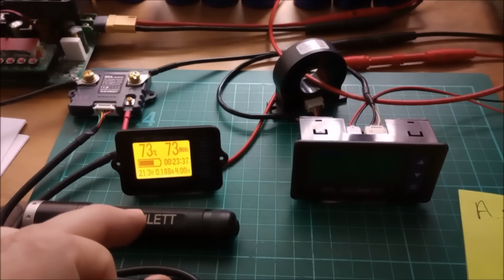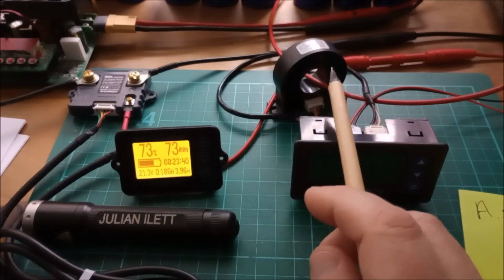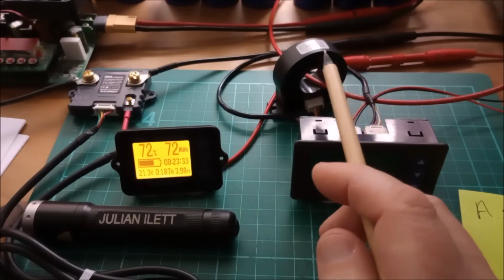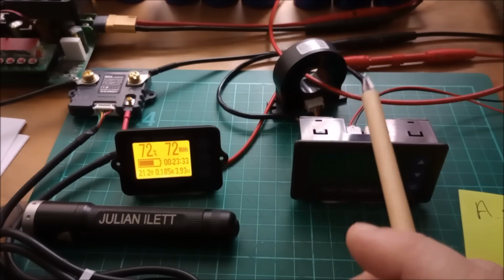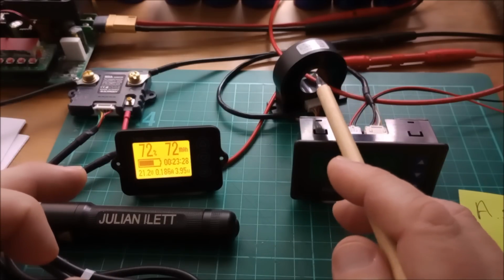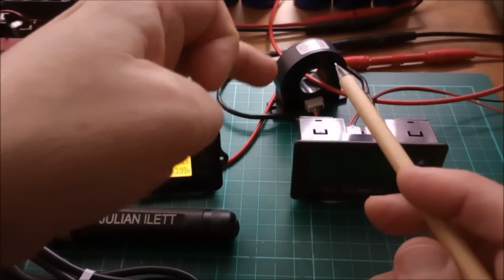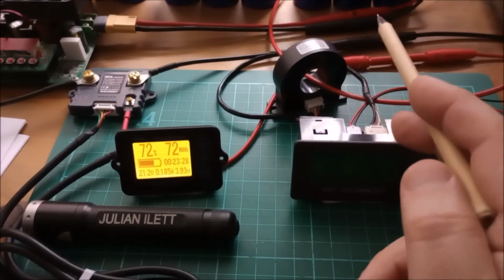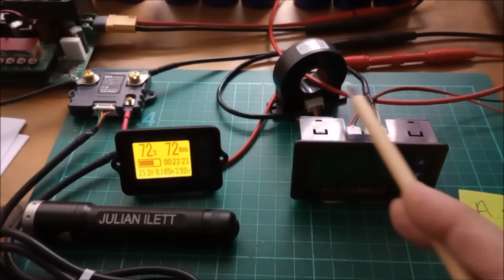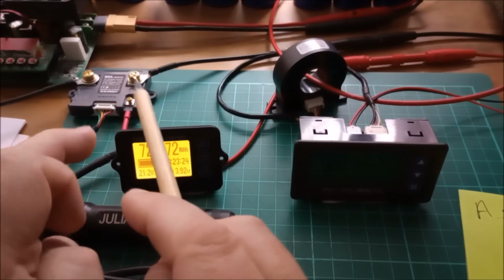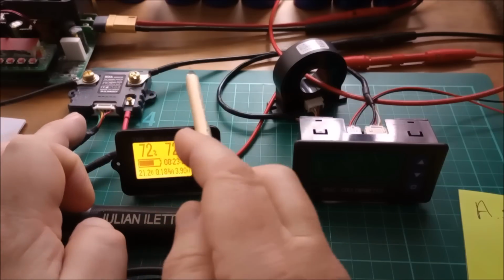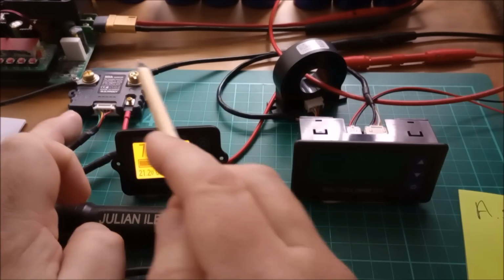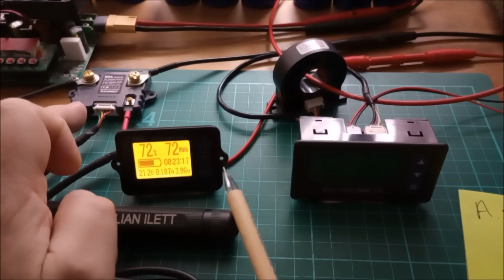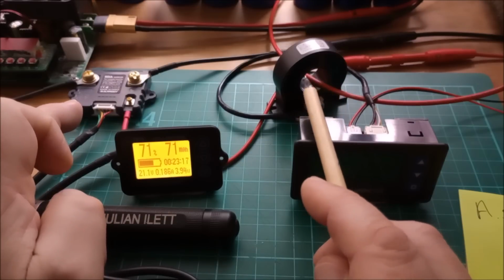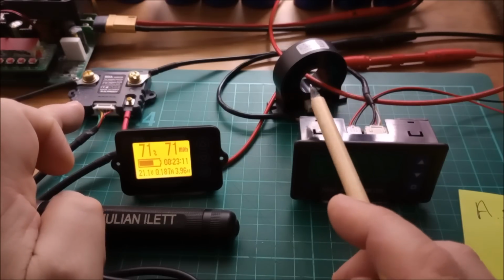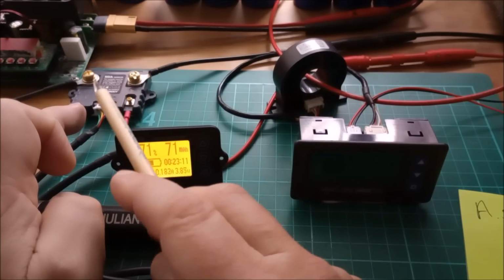The advantage of not having to break your circuit because this uses a current transformer is kind of defeated by the fact that this current transformer can't be opened and closed. So you do have to break the circuit in order to pass the wire through it, and you also have to break the circuit to connect through the current shunt on the TK15. So I don't really see that this has a lot of advantages over the standard current shunt.